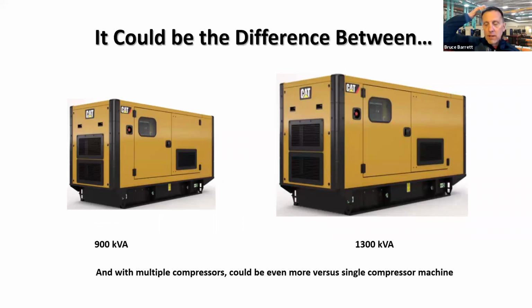What does that mean for low inrush? Well, we just closed the largest air-cooled job in our history. It's about $30 million. We were the highest priced chiller. We're the most efficient chiller. But when they started adding up the reduction in size for their generators, we now became the best value total first installed cost.